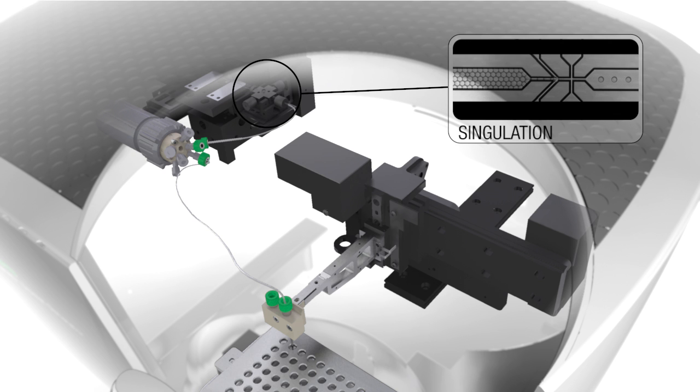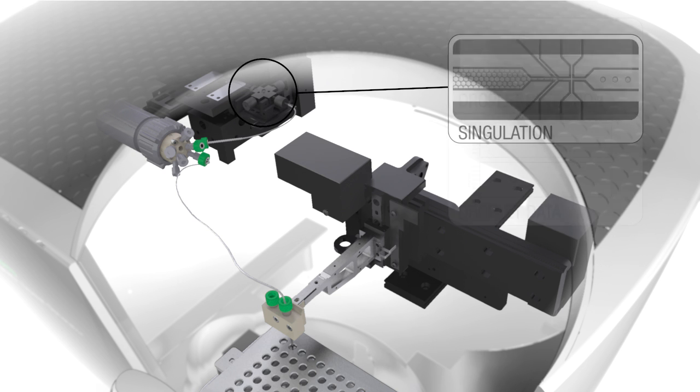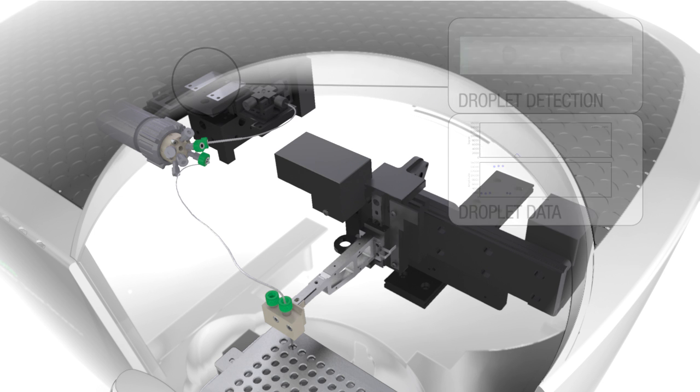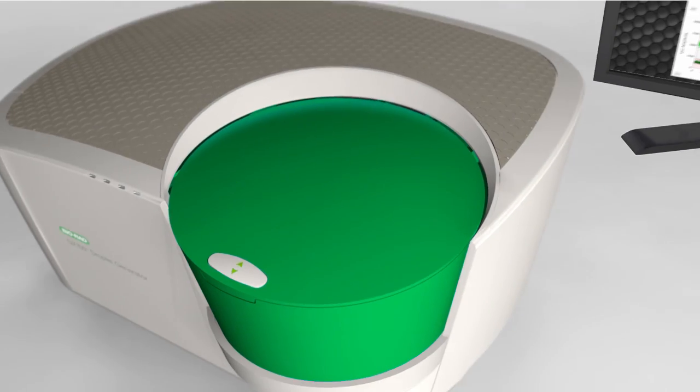The droplet reader automatically sips each sample, singulates all the droplets from a sample, and then streams them in a single file past a two-color fluorescence detector. The detector reads each droplet in turn at the rate of thousands of droplets per second and determines which droplets emit fluorescence and which do not.